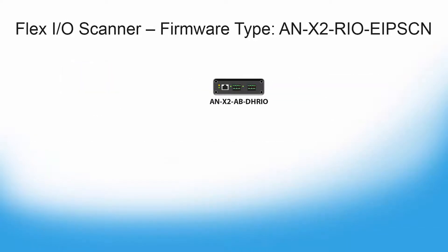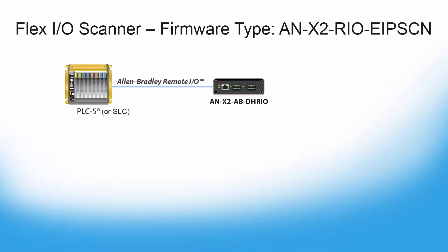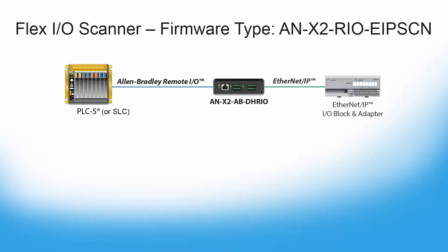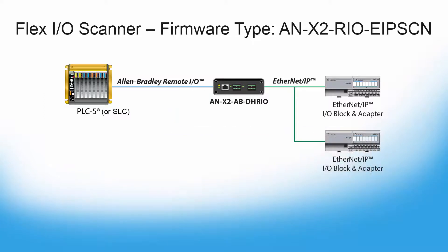The ANX2RIO EIP-SCN firmware is intended specifically to function as a flex IO scanner. This mode allows PLCs on remote IO to connect to and control 1794 AENT Ethernet IP flex adapters, so that you can replace your old IO with newer Ethernet IP based flex IO. This is probably the sole application that you would ever use this firmware for.